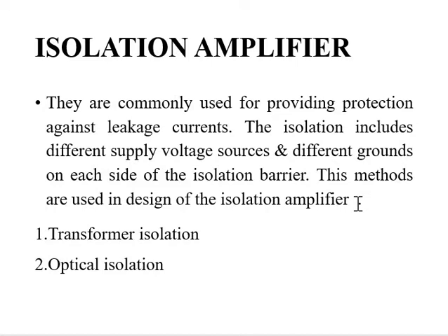So how is this isolation happening in biomedical instrumentation? This isolation is done by two techniques: transformer isolation and optical isolation.